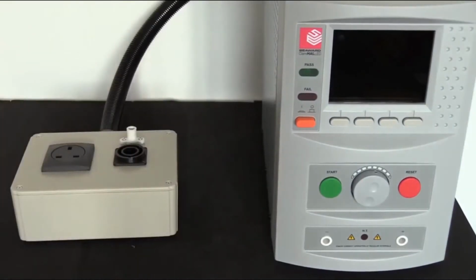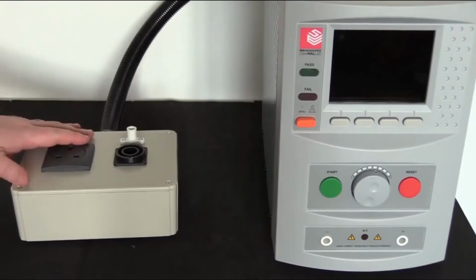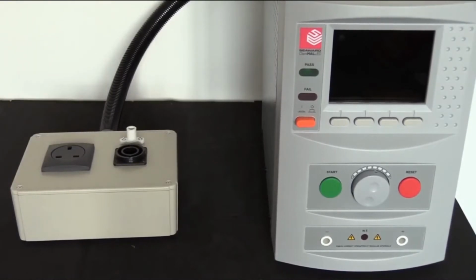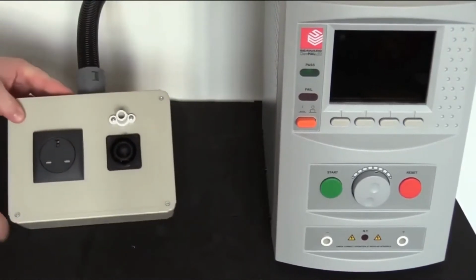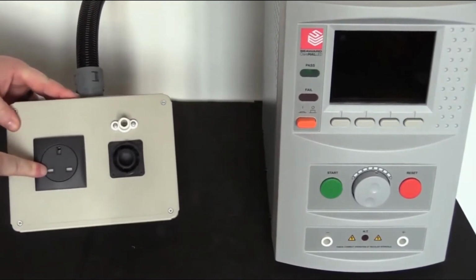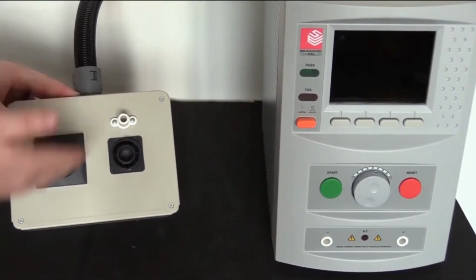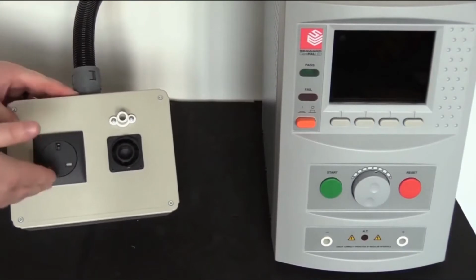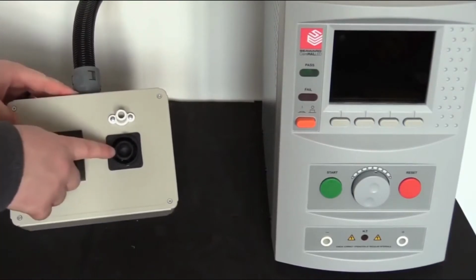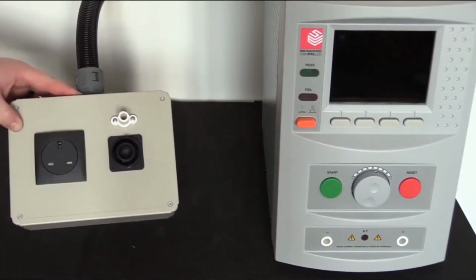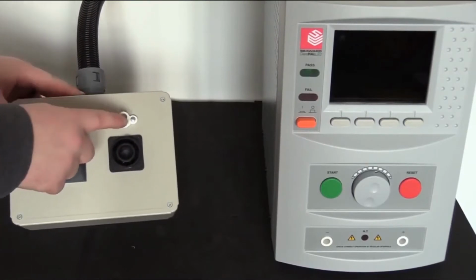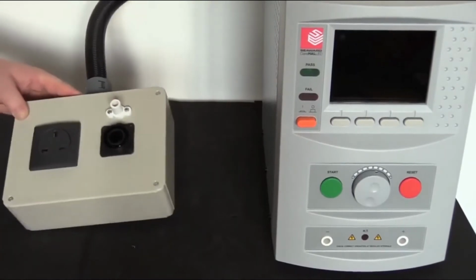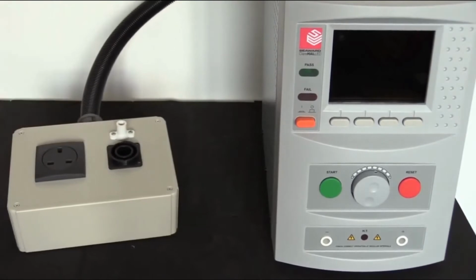If you have a 103 or 104 or an LED model of the unit, tests can be made via a rear connection connected to our output box. On our output box there are three main connections. You'll see there is an output plug socket. This can be regional, so we do have variants for Europe, Australia, America. We have a port for our Earthbond probe, and we also have a Hipot return for anyone manufacturing class 2 products. So for an Earthbond test, let's start there.